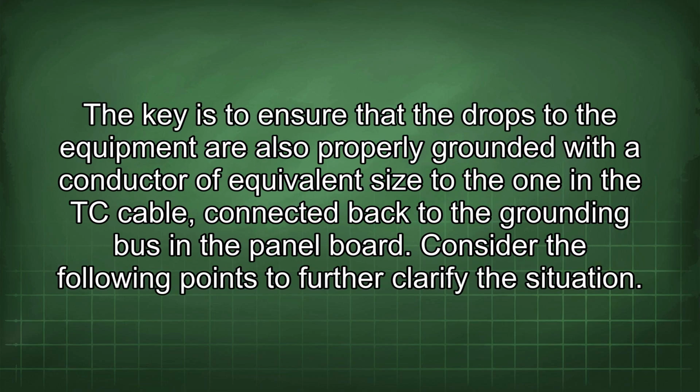The key is to ensure that the drops to the equipment are also properly grounded with a conductor of equivalent size to the one in the TC cable, connected back to the grounding bus in the panel board. Consider the following points to further clarify this situation.